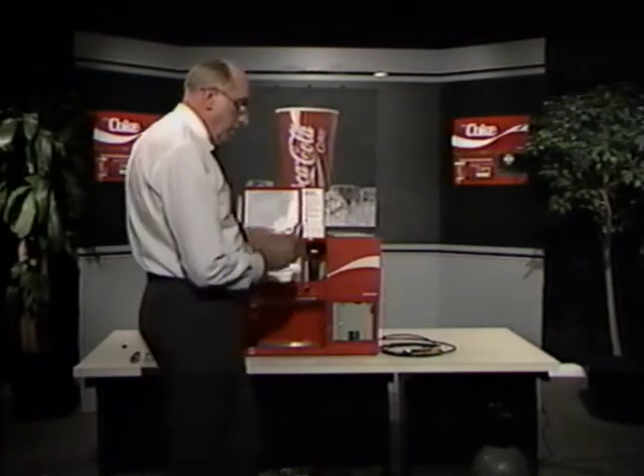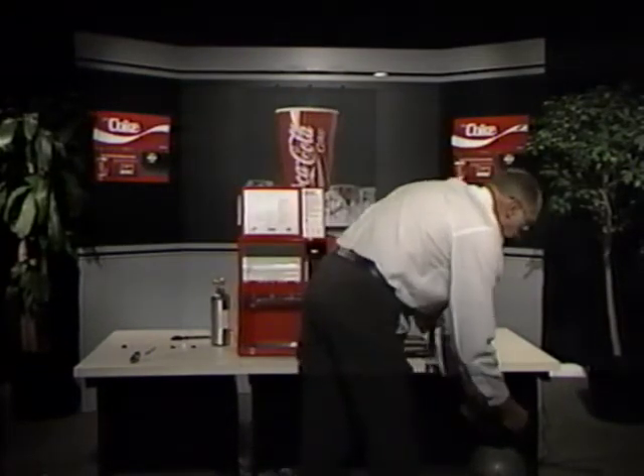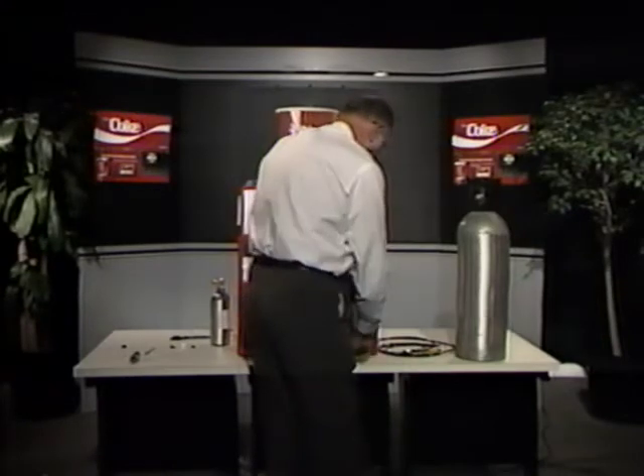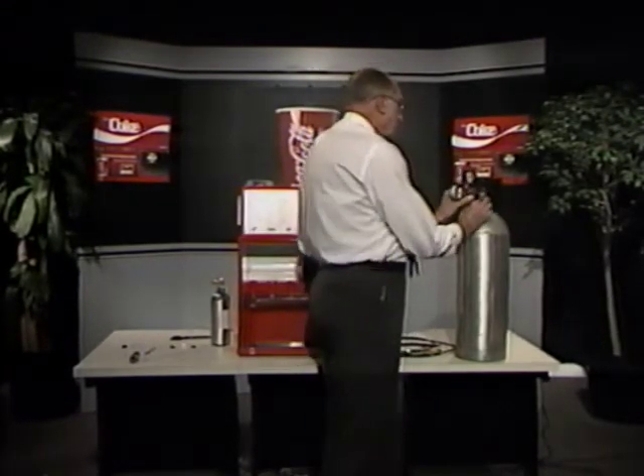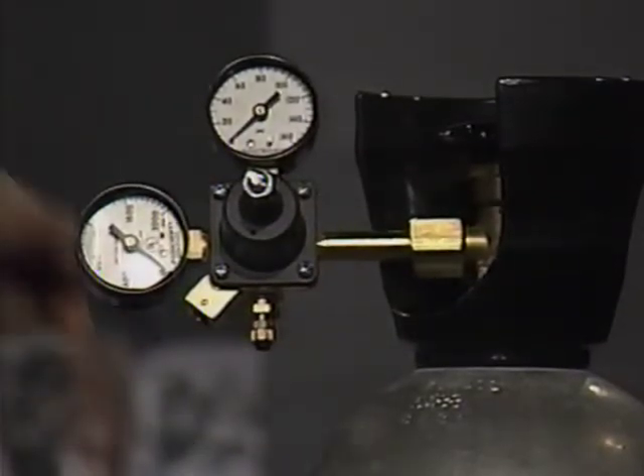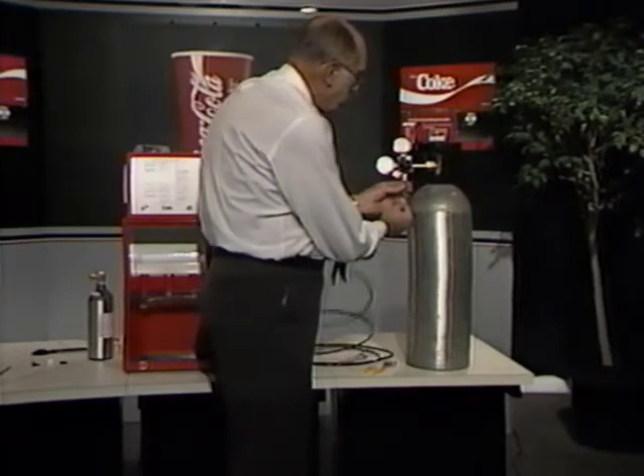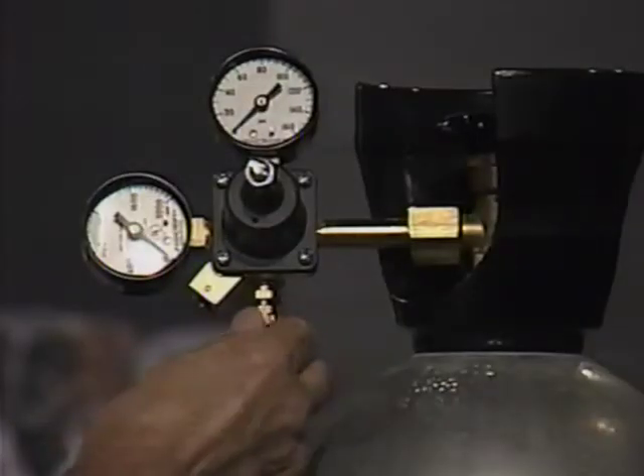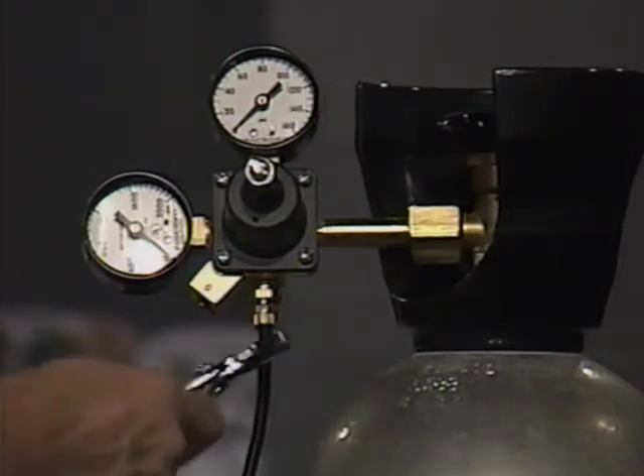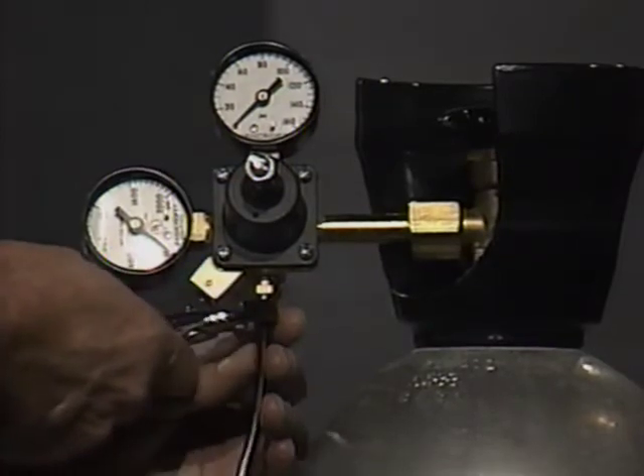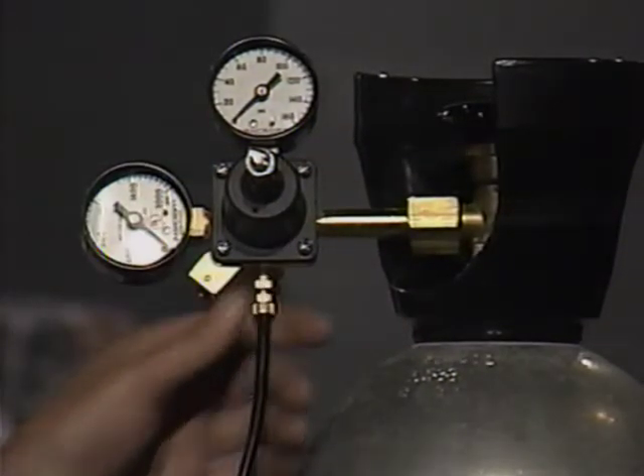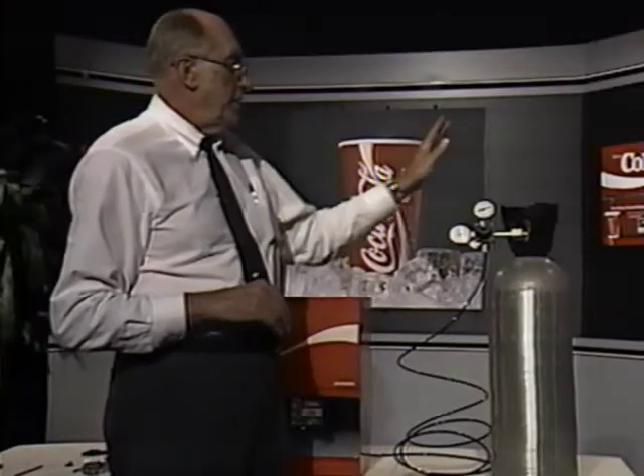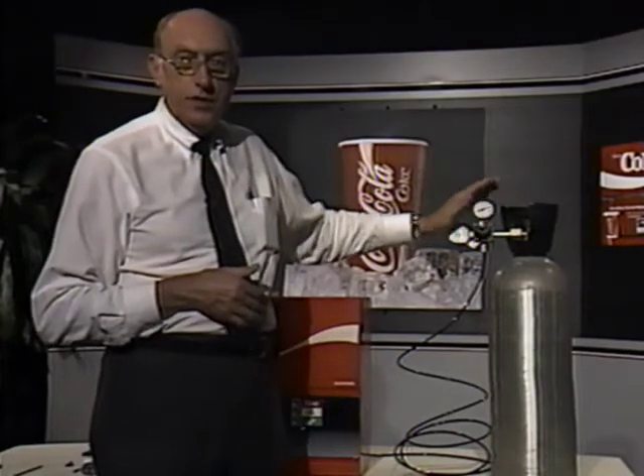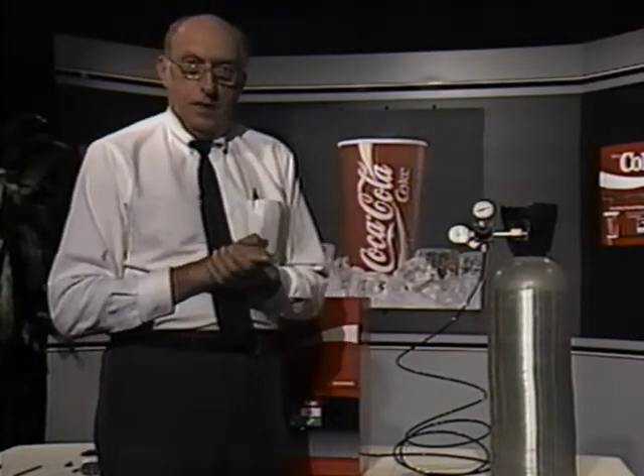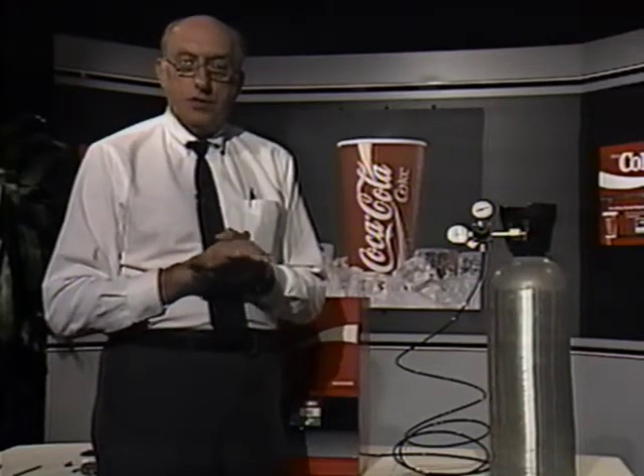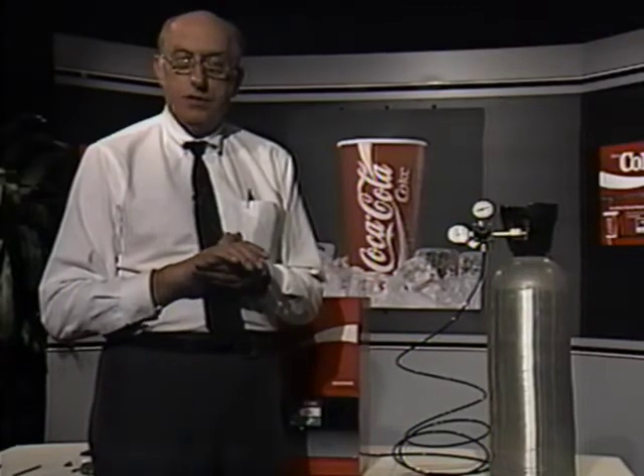And the next step will be to install the CO2 regulator. And finally, we'll install our extension hose into the connection to the CO2 regulator. And that's all it takes to connect the system. All that's necessary now is to set the regulator for 120 pounds and to test your system for leaks. There is a complete set of instructions with each kit, so you have the testing procedure available to you when you install the unit.